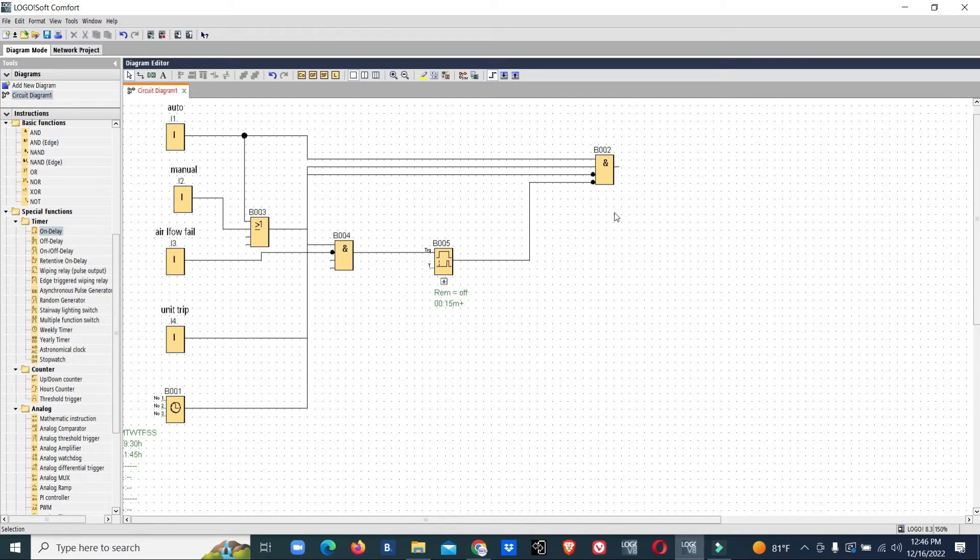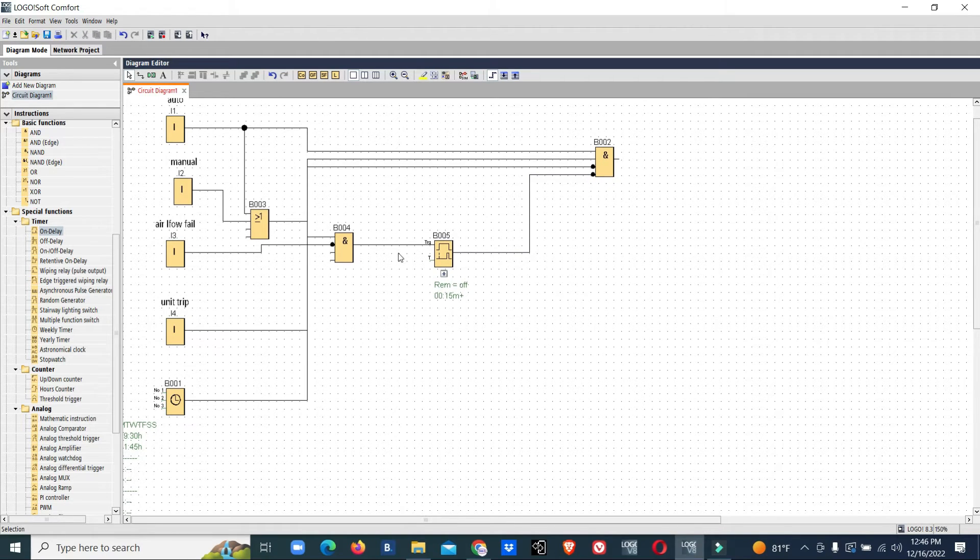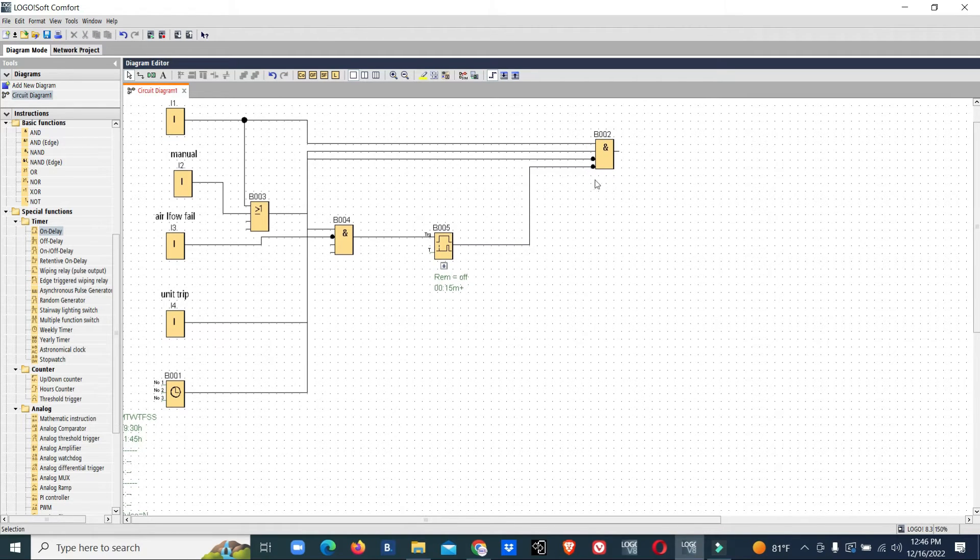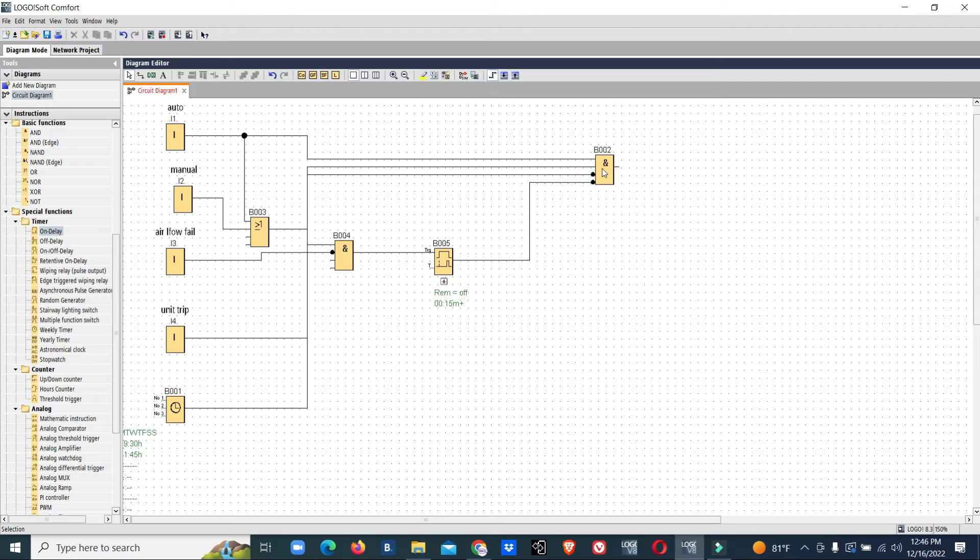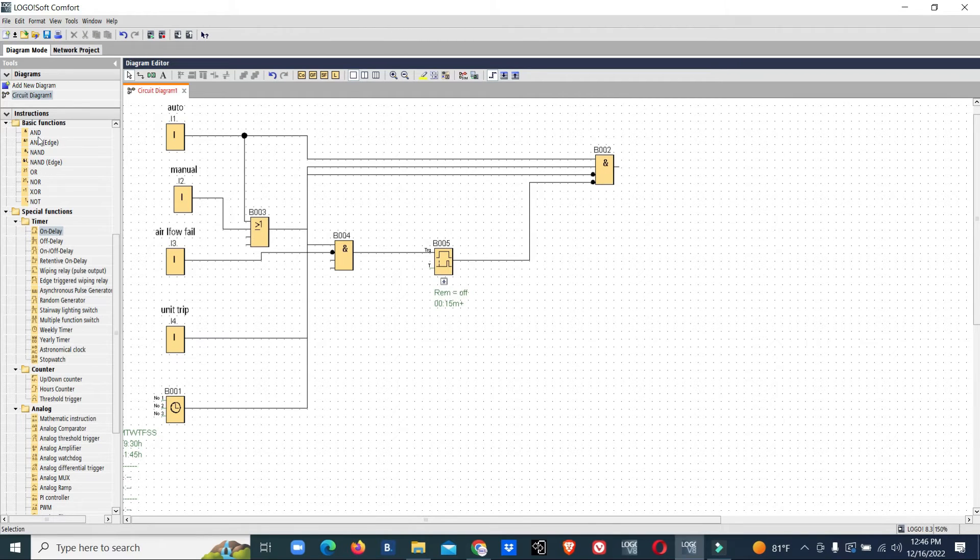So if the unit started and within 15 seconds the airflow feedback doesn't reach the PLC controller, it should stop.